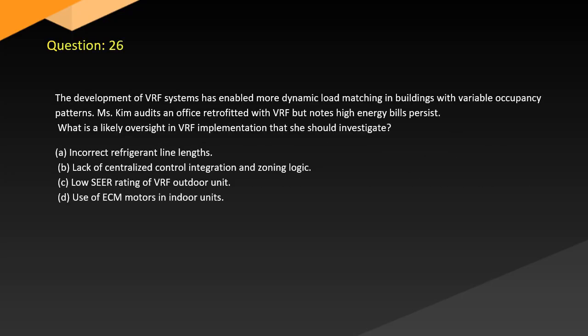Question 26. The development of VRF systems has enabled more dynamic load matching in buildings with variable occupancy patterns. Ms. Kim audits an office retrofitted with VRF but notes high energy bills persist. What is a likely oversight in VRF implementation that she should investigate? A. Incorrect refrigerant line lengths. B. Lack of centralized control, integration, and zoning logic. C. Low SEER rating of VRF outdoor unit. D. Use of ECM motors in indoor units.